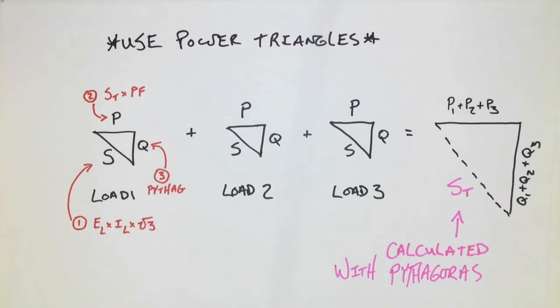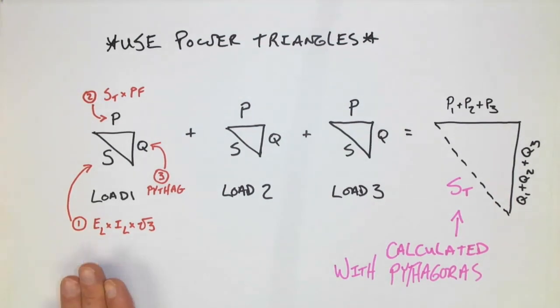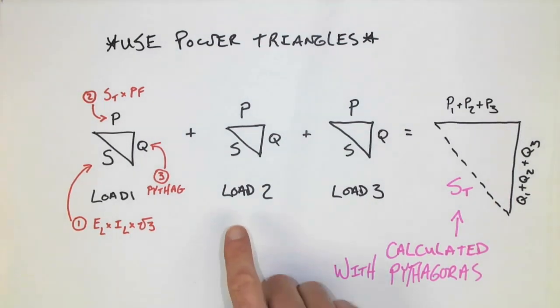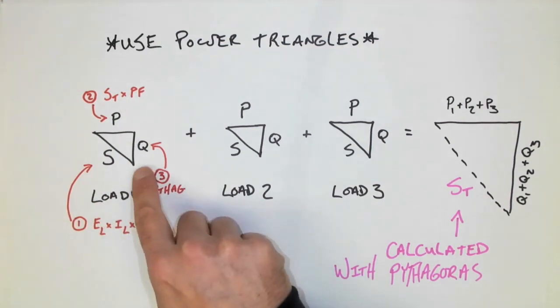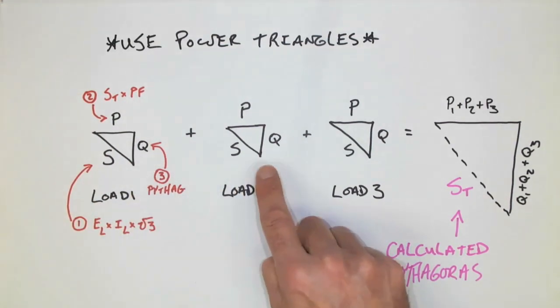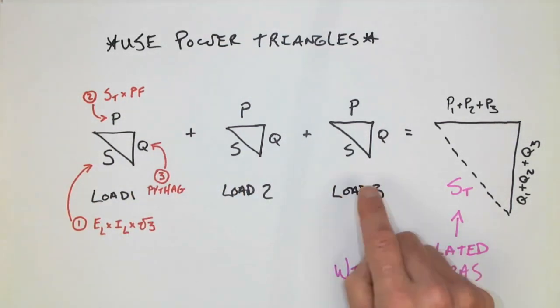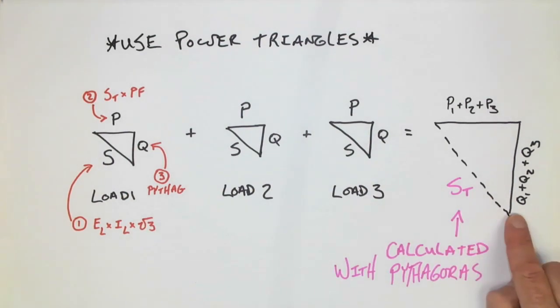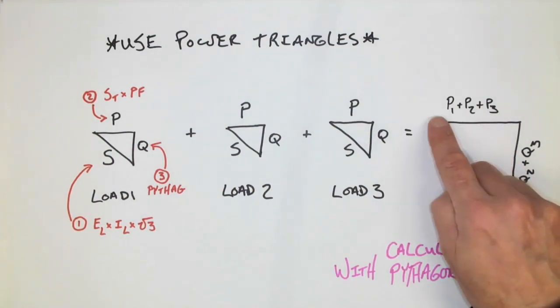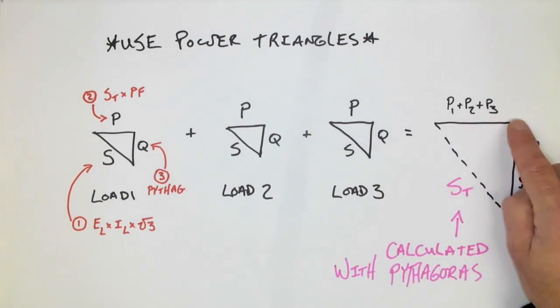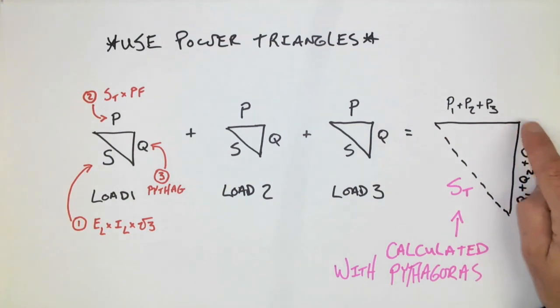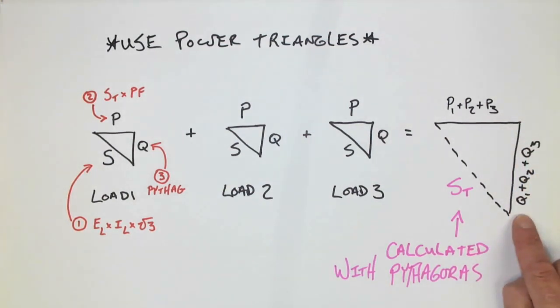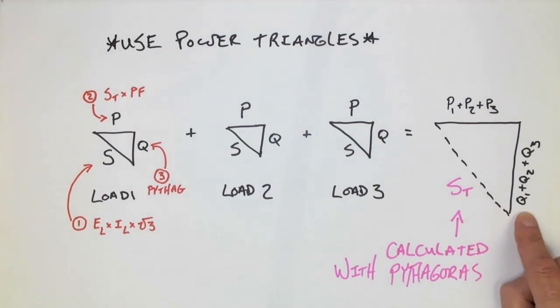Often, a method that I will use is to first, for each individual load, sketch a power triangle. In order to work out the totals for the circuit, I am then going to add the horizontal components of each of the power triangles and add all of the reactive components, keeping in mind that inductive and capacitive loading — the VARs will cancel each other out.